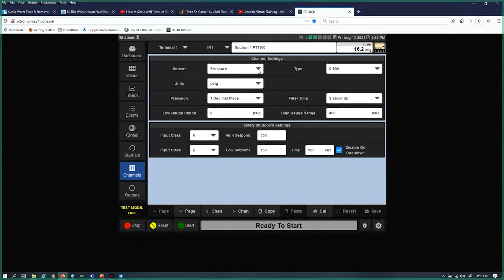Low gauge range and high gauge range. So I had a gentleman trying to set up a panel the other day, and in his case, he had a 4 to 20 milliamp pressure transducer. So instead of saying pressure here, he said current loop because he was doing a 4 to 20. Well, that's fine. In fact, I'll just do that. So he had a current loop for his sensor, a 4 to 20 milliamp. He had his custom units. We'll just make some up, PSIG. And everything looked pretty good. And it turned out that his pressure transducer was a 0 to 1,000 pound.